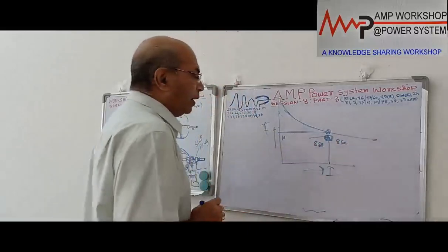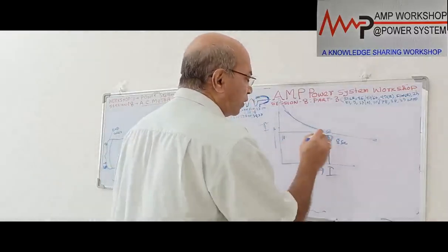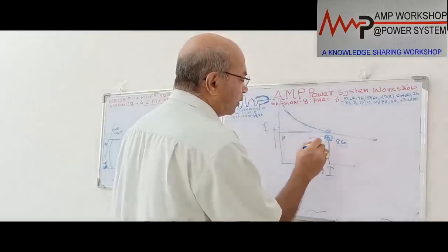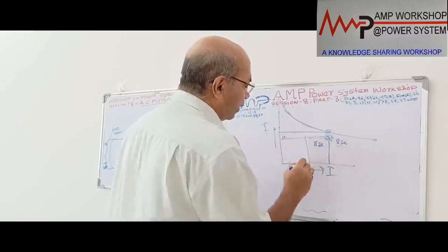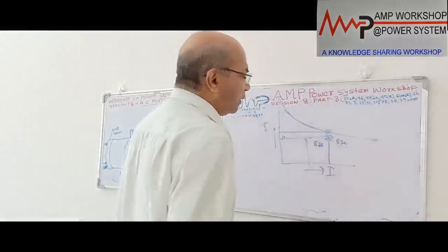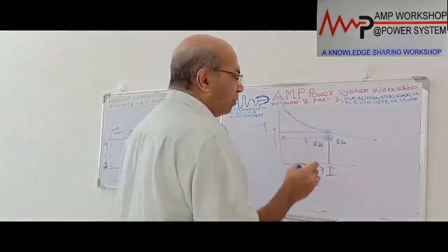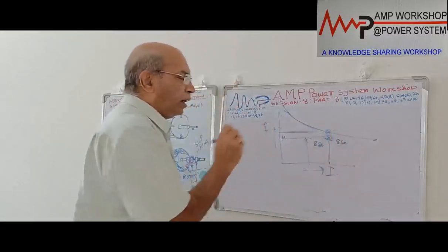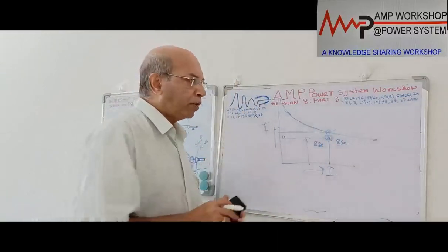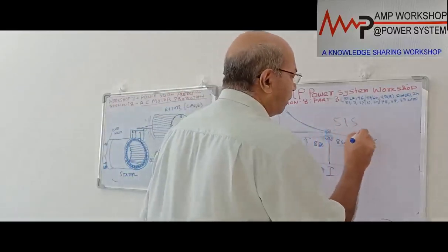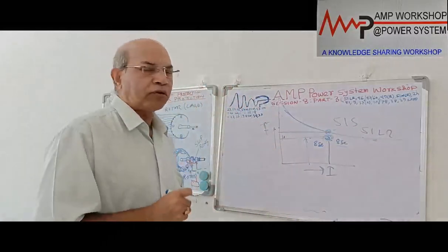If that is the case, and the motor fails to start, then we cannot wait up to 10 seconds, because the motor locked rotor withstand time at 6 times current is only 8 seconds. Within 8 seconds the motor will burn, but I would have to wait up to 10 seconds. In that case, we cannot use the previous method, the locked rotor protection 51S, or we say 51LR, through the CT which we provide. We cannot protect the motor with this.